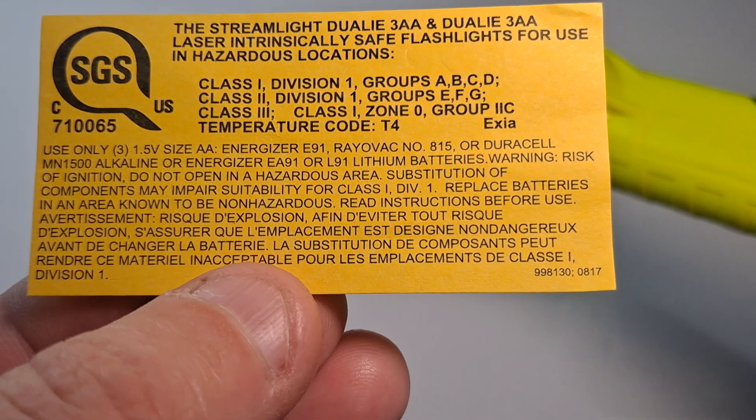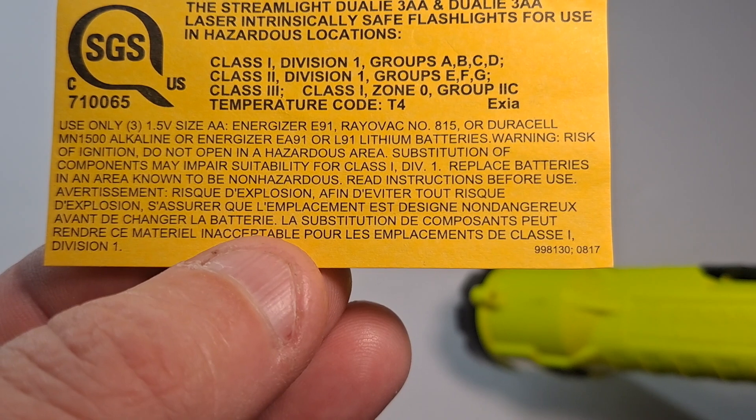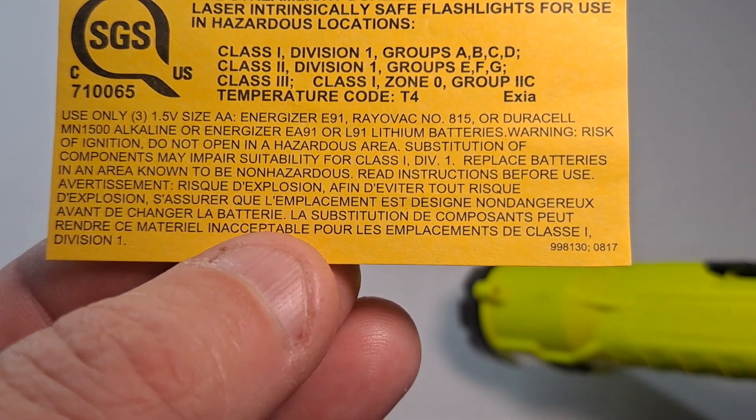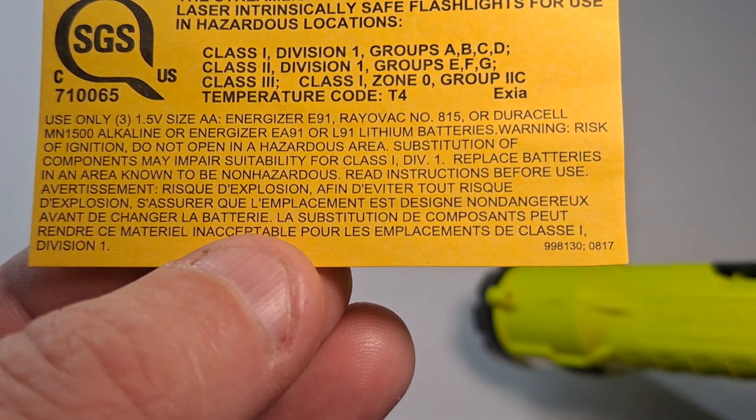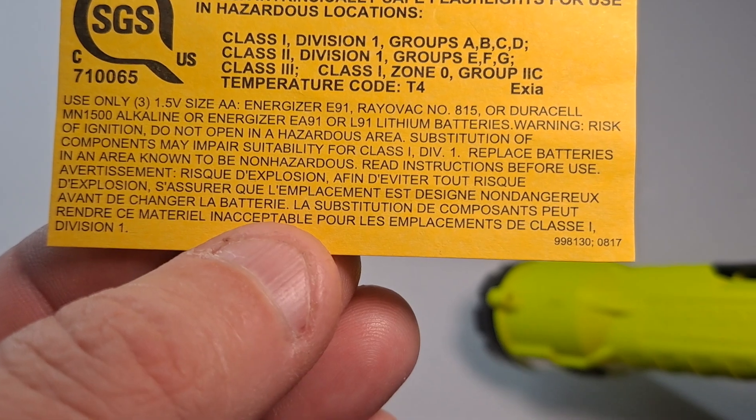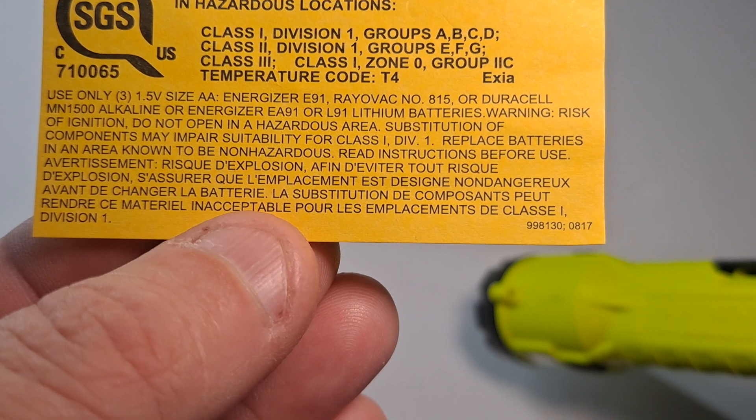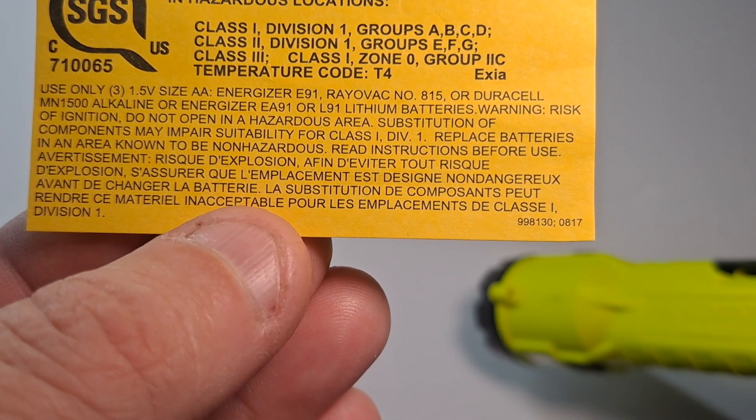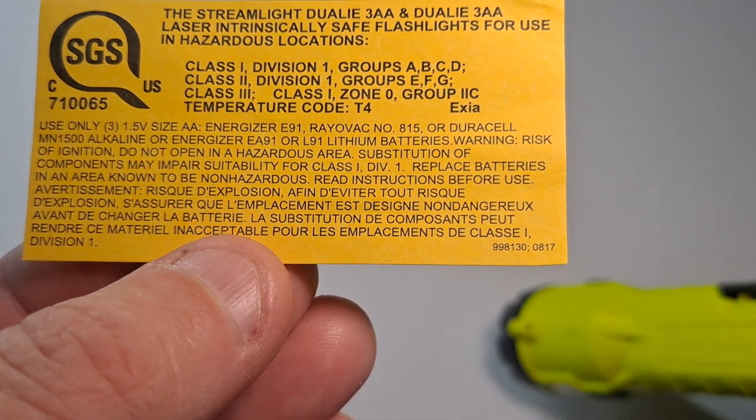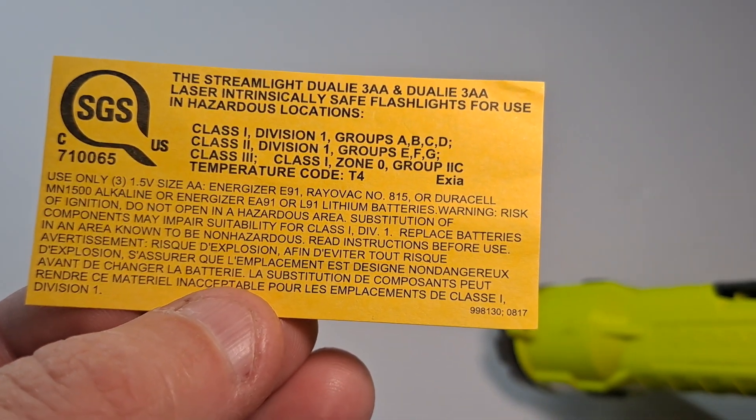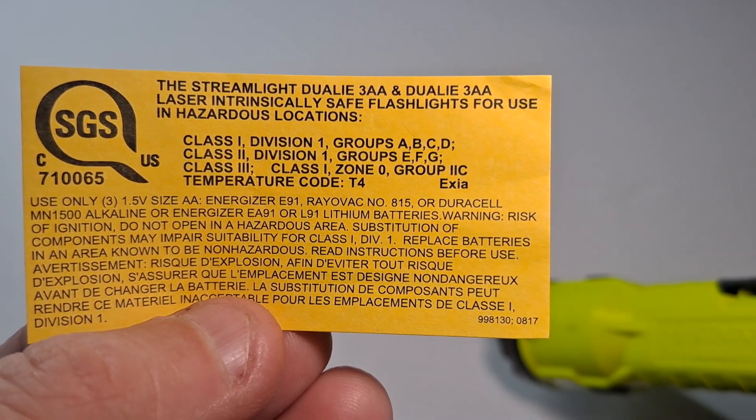Use only three 1.5 size AA Energizer E91s, Rayovac number 815s or Duracell MN 1500 alkaline or Energizer EA91 or L91 lithium batteries. Risk of ignition do not open in hazardous area. Substitution of a component may impair its suitability for Class 1 Division 1. Replace batteries in an area known to be non-hazardous. Read instructions before use. The reason they're recommending only those batteries is those are the only ones classified in their testing.